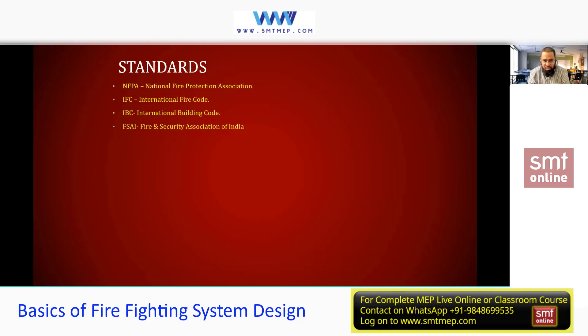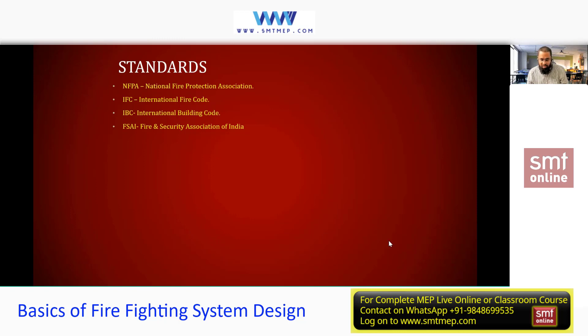As per the course title, we'll follow Chapter 3 and Chapter 9 of IBC. Chapter 3 gives us the types of buildings, and Chapter 9 in IBC is specifically for firefighting systems. IBC will help you get an idea about which system is applicable. IBC is not for the actual design of the firefighting system — it's to determine which system is applicable as per the type of building. Architects know the building type, so using Chapter 3 and Chapter 9 together we can identify the required system.